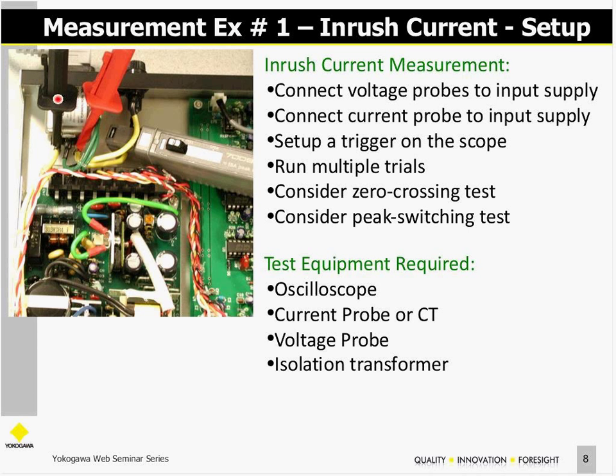One side is neutral, the black probe here, one side is the hot side, the red probe. I've got a current probe, and I've got the current sense on it in the proper direction - there's a little arrow there that points towards the power supply. That's a fuse block on the back diagram, so I'm in front of the fuse, right at the mains. I have an RFI EMI filter there that's made it pretty easy to access this little switch mode power supply, a commercial design that I've modified for these measurements.